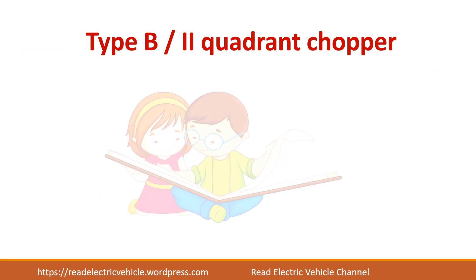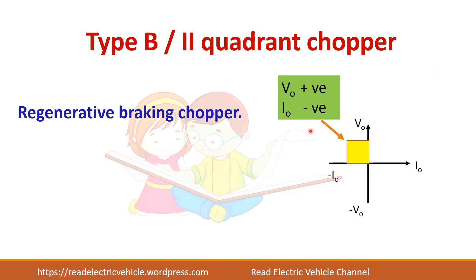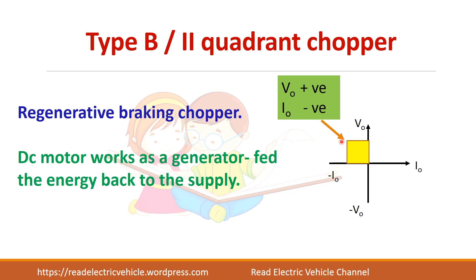So what is a second quadrant chopper? If it operates in the second quadrant, the voltage is positive and the current is negative, so the power will be negative. This is a braking operation, and in this mode the DC motor will work as a generator and feed the energy back to the supply.